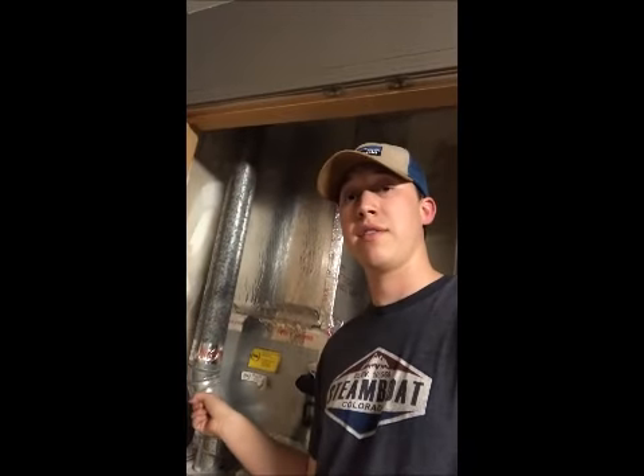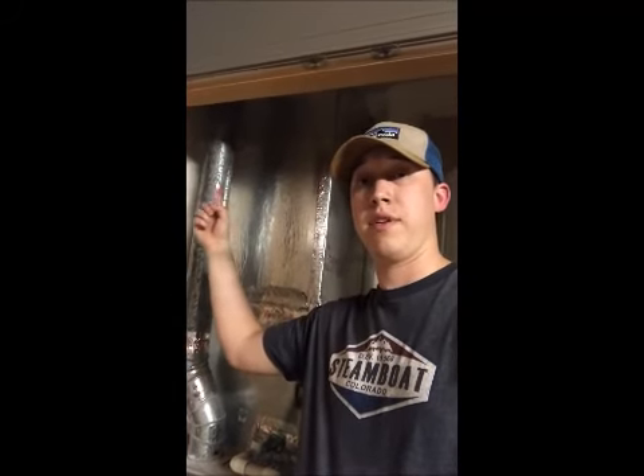Alright guys, I want to take this time to bring up an issue I had this last winter. We just moved into this house last year, so it's the first time I've encountered this problem. So right here we got the flue vent, like I mentioned earlier. Right here it's a 4-inch vent. Into the ceiling it's also a 4-inch vent. And then in the attic it goes from a 4-inch to a 3-inch. You should never have a flue vent decrease in size while you go up.